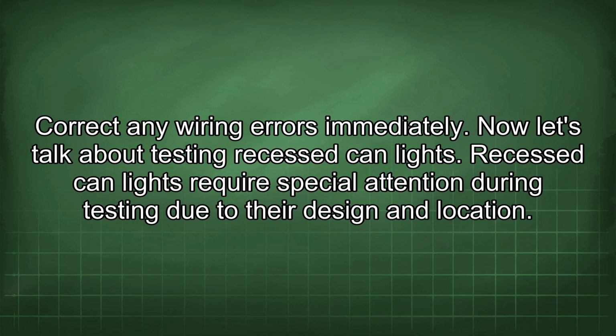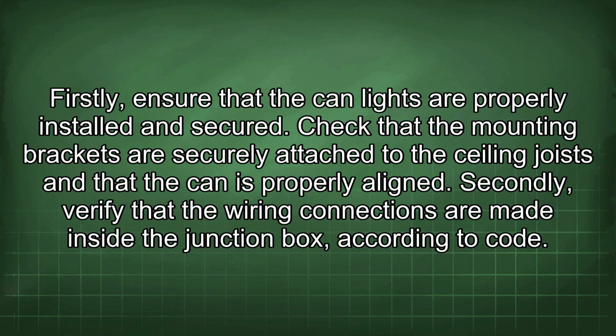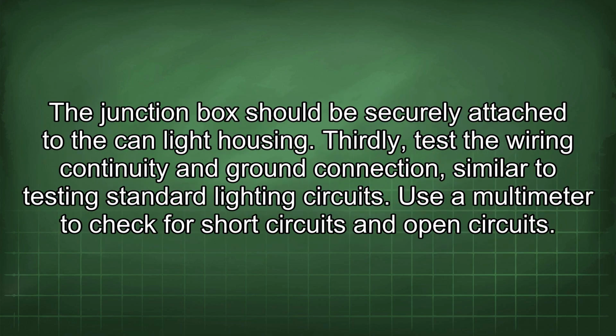Now let's talk about testing recessed can lights. Recessed can lights require special attention during testing due to their design and location. Firstly, ensure that the can lights are properly installed and secured. Check that the mounting brackets are securely attached to the ceiling joists and that the can is properly aligned. Secondly, verify that the wiring connections are made inside the junction box according to code. The junction box should be securely attached to the can light housing.